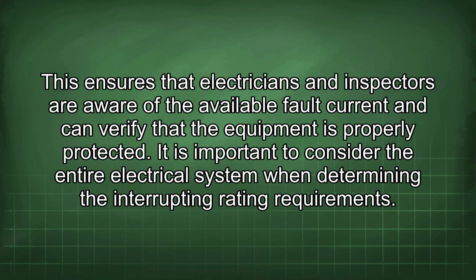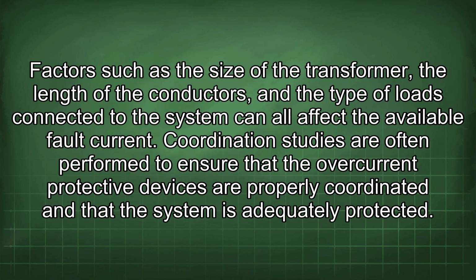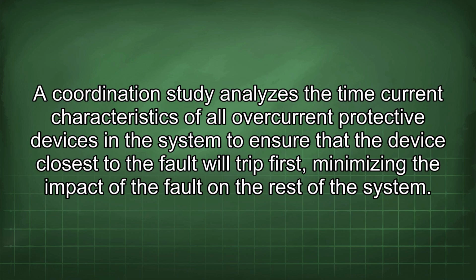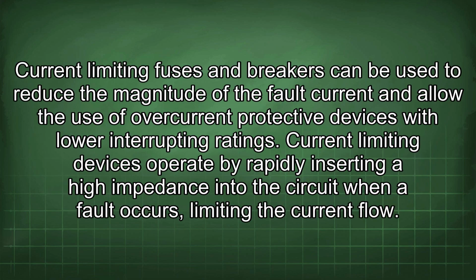It is important to consider the entire electrical system when determining the interrupting rating requirements. Factors such as the size of the transformer, the length of the conductors, and the type of loads connected to the system can all affect the available fault current. Coordination studies are often performed to ensure that the overcurrent protective devices are properly coordinated and that the system is adequately protected. A coordination study analyzes the time current characteristics of all overcurrent protective devices in the system to ensure that the device closest to the fault will trip first, minimizing the impact of the fault on the rest of the system.